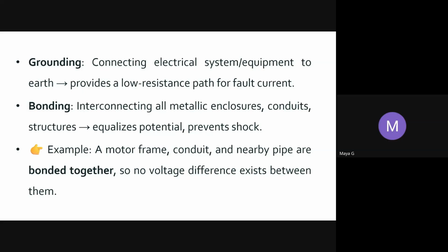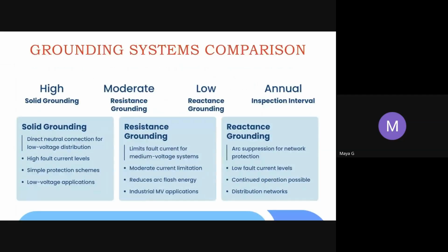Example, a motor frame, conduit, and nearby pipes can be bonded together, so no potential difference exists between them. So this particular chart gives the three methods and their comparisons: solid grounding, resistance grounding, and reactance grounding. Solid grounding directly connects the neutral to the earth, and it is used for high fault current, where simple protection schemes are applied. Resistance grounding reduces the arc flash energy, and it is usually applied for industrial medium voltage applications. And reactance grounding is used in distribution networks.